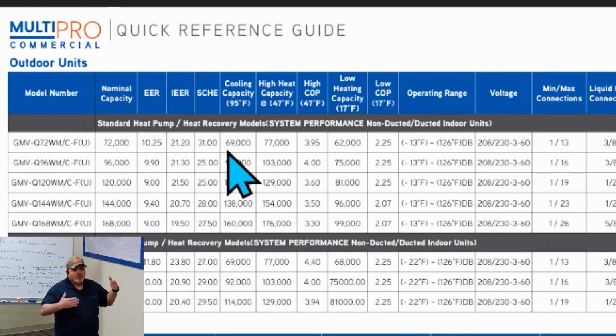Your best option may be, let's say we needed 20 ton, to do 4 or 5 tons - obviously we don't have 5 tons in single phase, so you do 4 six-ton units. You understand what I'm getting at? Split it up, so that way when a machine goes down, you don't lose the whole building.